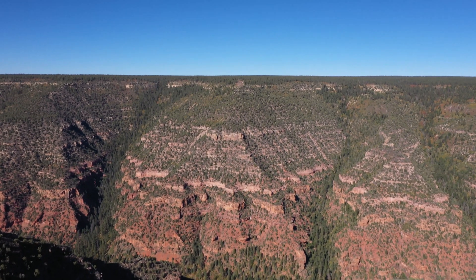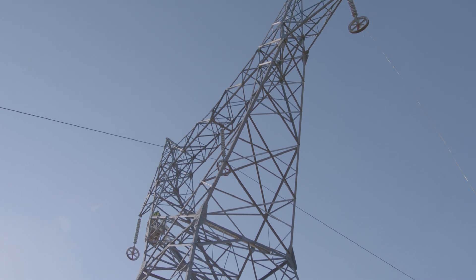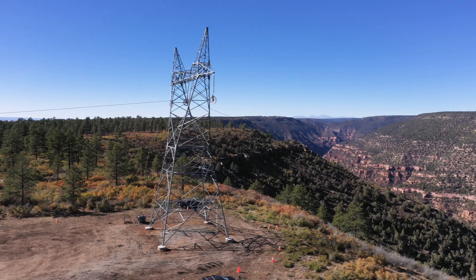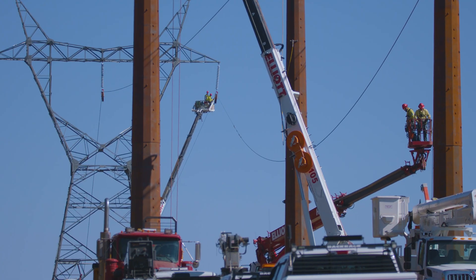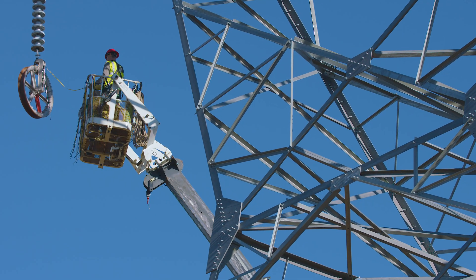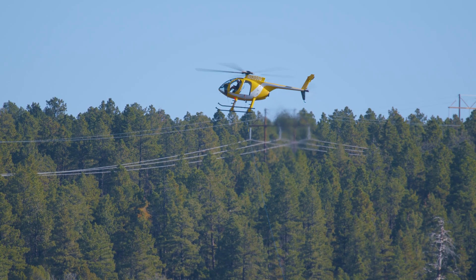You're talking about on the order of a hundred thousand pounds of tension hanging off of these lattice structures and the associated dead-end structures that are behind them. The line is drawn by a special conductor called 1272 KT ACSR, made in Japan, and today it was strung by helicopters flying across the canyon.